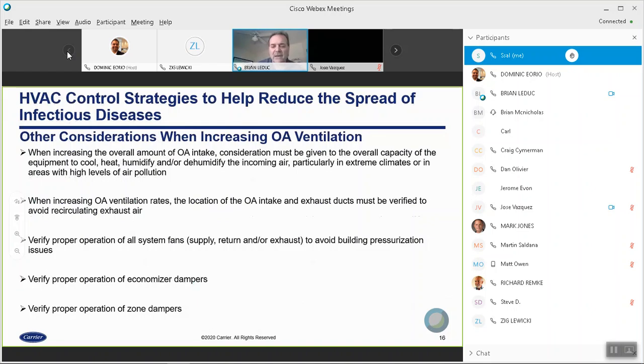You also want to, as part of your startup evaluation, make sure the condition of the OA intakes are okay. Make sure that the building wasn't designed where the exhaust and the OA intake are right next to each other, which is obviously going to cause recirculation of the air, which goes against the whole purpose of increasing the ventilation rate. You want to make sure everything's working right. Your supply fans, your return fan, your exhaust fans. Your economizer has to be working correctly. You have to make sure your zone dampers are working correctly. So that all kind of talks to a recommissioning recommendation when restarting a building that has been offline for a significant amount of time.